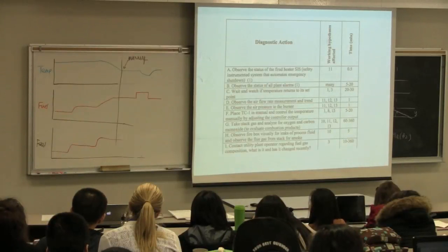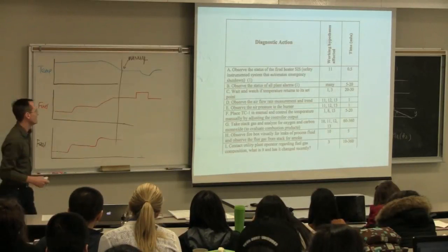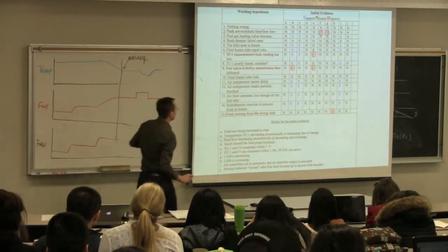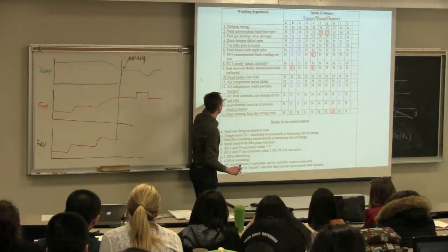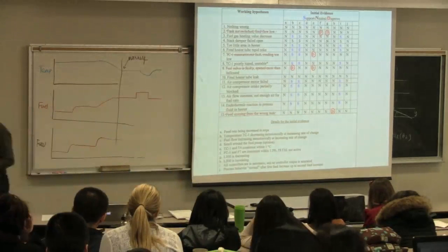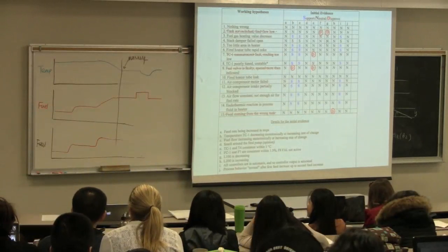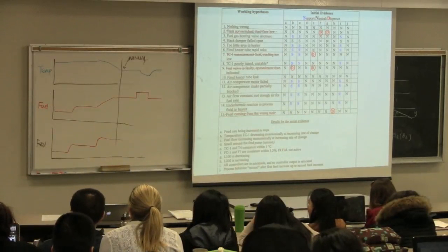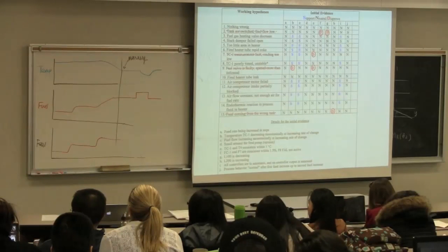Does that help us, this diagnostic action? It does show us and verifies that that control loop might have been unstable, but also it indicates to us that there's something with my airflow. Okay, if I'm changing my fuel and I'm increasing my fuel, but my temperature drops off, one thing to recognize is that my airflow to that furnace is not at the right level. Okay.